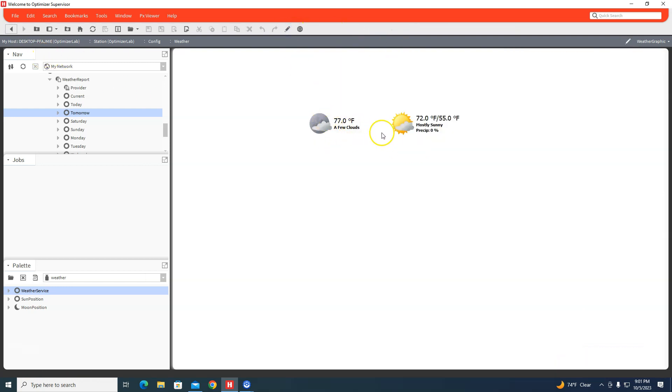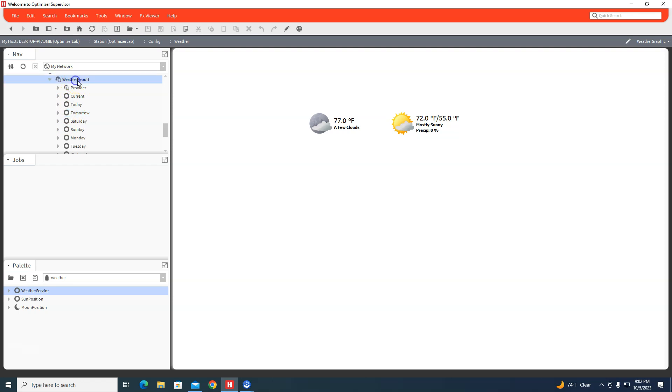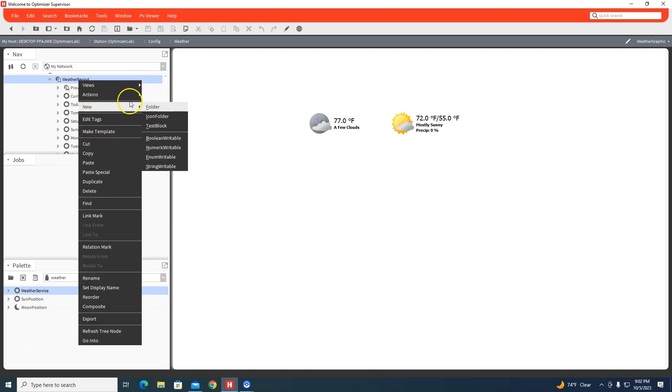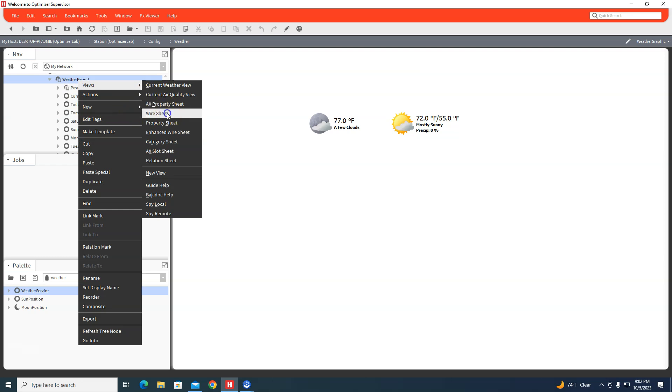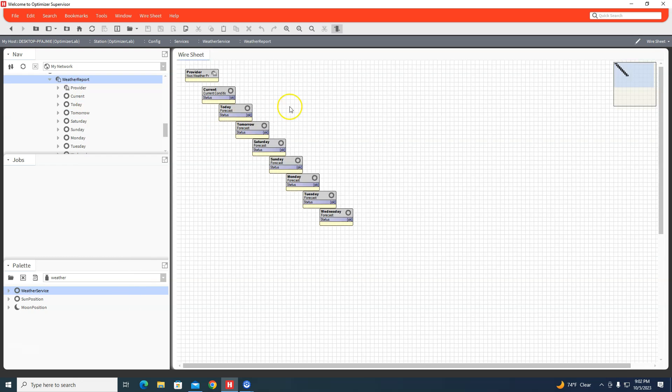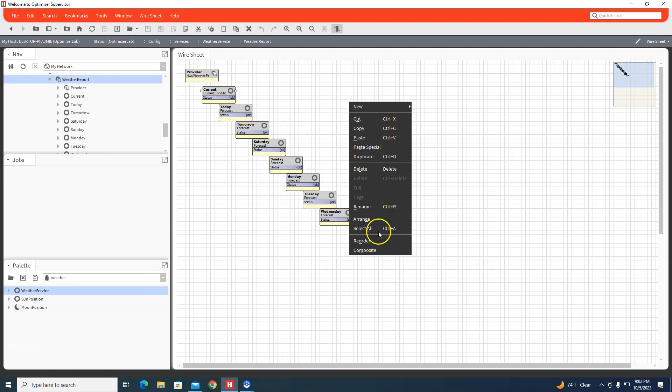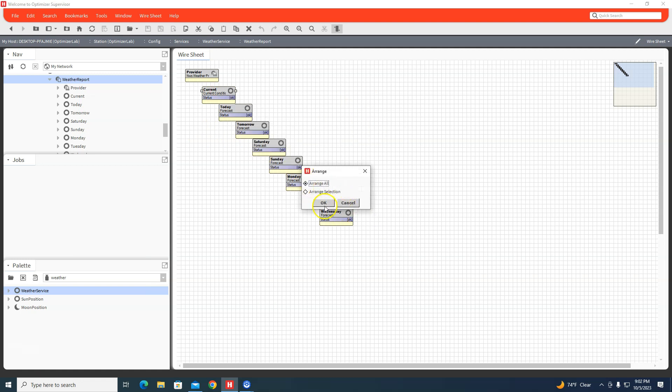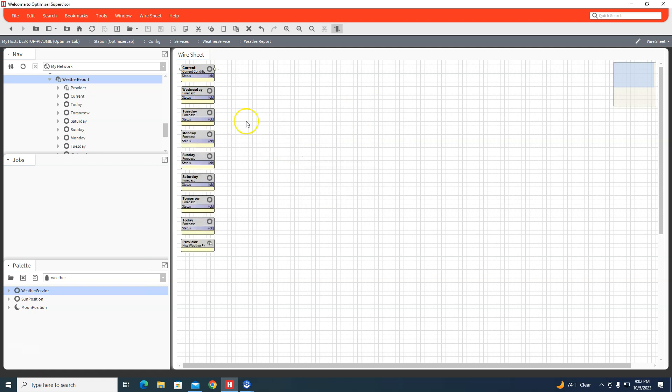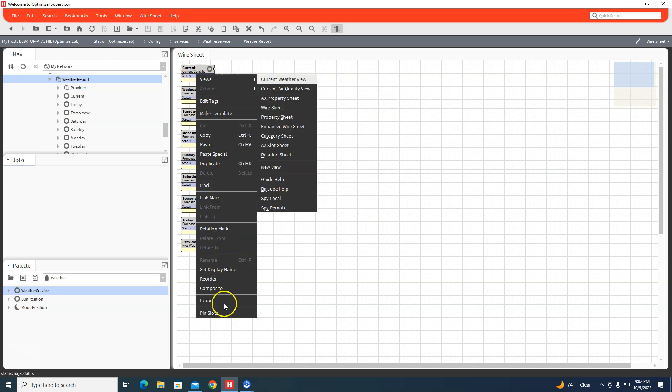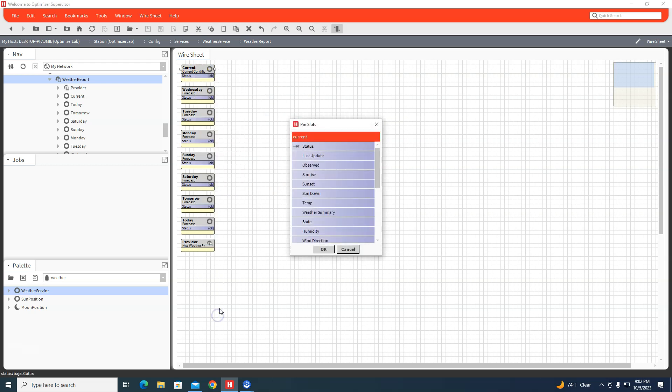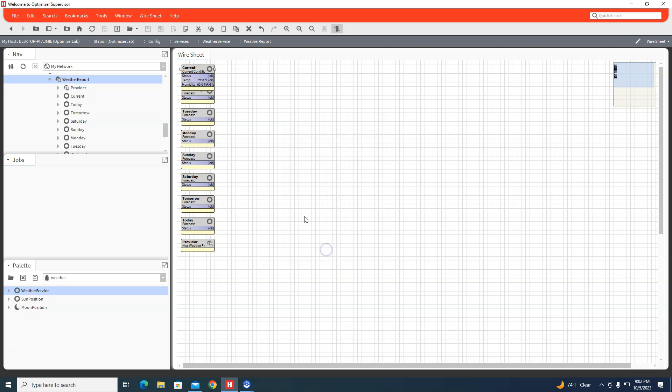What you can also do is, say you have some global outdoor air shared with only one sensor - you can go into the weather service wire sheet. You can take the Current, pin slots, and take the current temperature and humidity and tie those into the fallback of the program you're using for outdoor air.